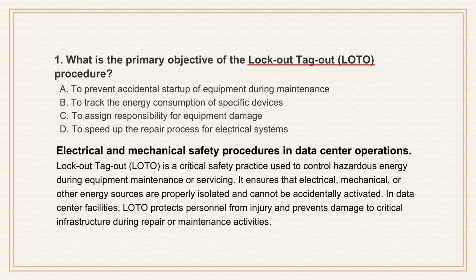The lockout-tagout procedure, or LOTO. So when we see this huge electrical gear, these enormous cooling systems, why is LOTO the absolute foundational procedure? Because a data center is full of hazardous energy, and I don't just mean electricity. The main goal of LOTO is to prevent the accidental startup of equipment while someone is working on it. Think about a giant fan unit or a big transformer—if you're near it or inside it and it suddenly turns on, the results can be catastrophic.